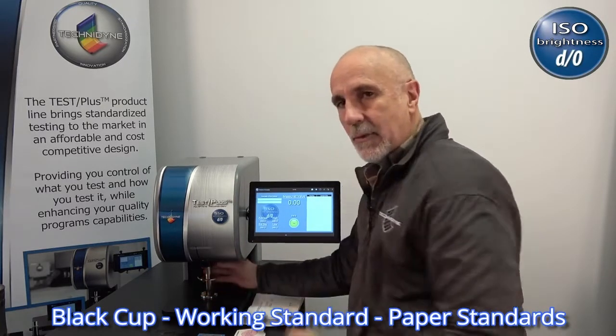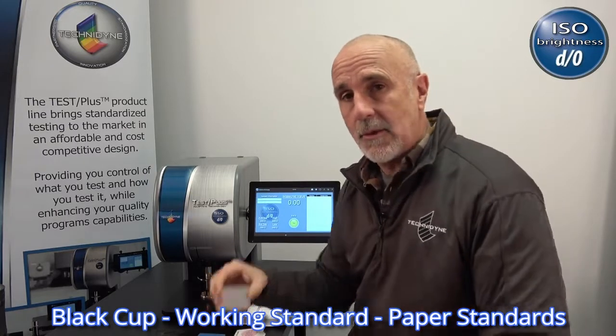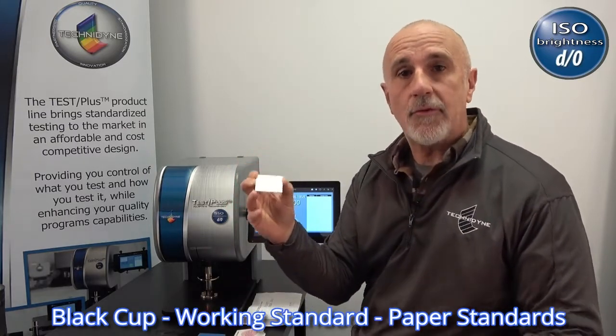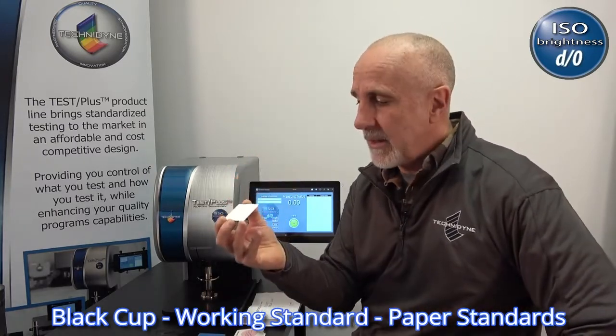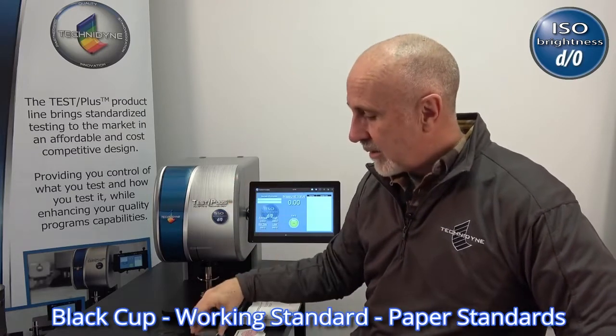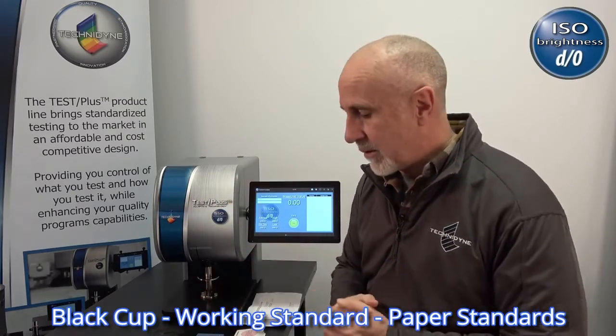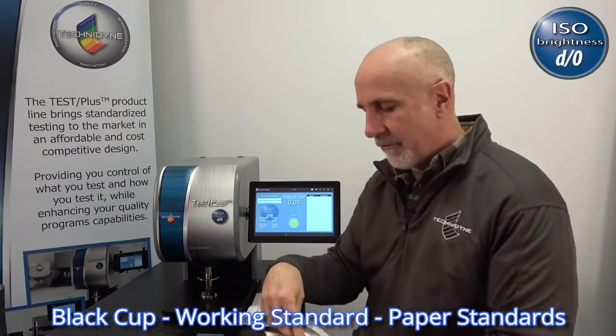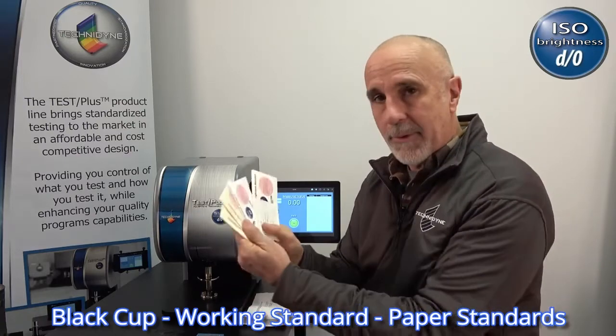Next thing you're going to need is the white ceramic working standard that also came with the original shipment of the instrument. So we're going to need this to reevaluate at the end of the calibration sequence. And most importantly, you're going to need a fresh set of paper calibration standards.